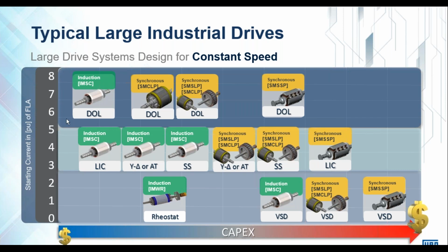And then in the high impact zone, a standard induction motor direct online is the cheapest or least expensive from a capex point of view. And then of course, if we need synchronous machines, it becomes a lot more expensive. I think the takeaway point here is, depending on the requirement of the power network supply, if you can get away with a high impact start from a large direct online motor, it is a robust and inexpensive solution.